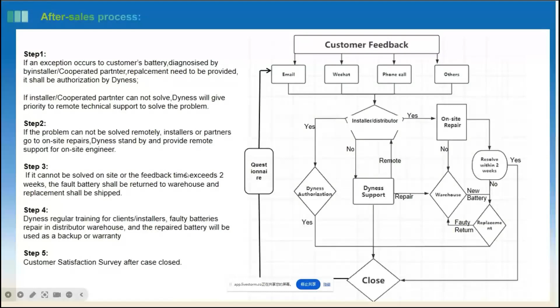Okay, if no question on this part, we'll move on to the technical part. The first is about communication failure during installation, because I do after-sales service and technical support. More than 80% of battery failure problems happen during installation. There are three elements during the installation: the communication cable, the battery dip switch settings, and the inverter battery mode selection.